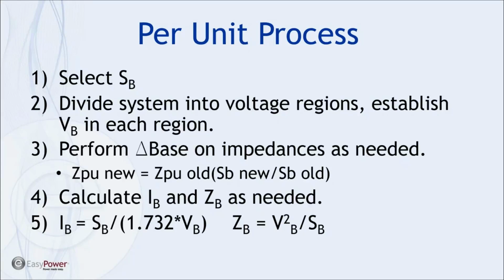So for a given system, we select a base kVA. For the examples I'm going to show you, I'm going to start with 2000 kVA. Then we take our system and divide it into voltage regions. The ones I've shown you so far only have two voltage regions, but we're going to add a third later on. Then we perform what I call a change of base, or a delta base, on impedances as it's needed.